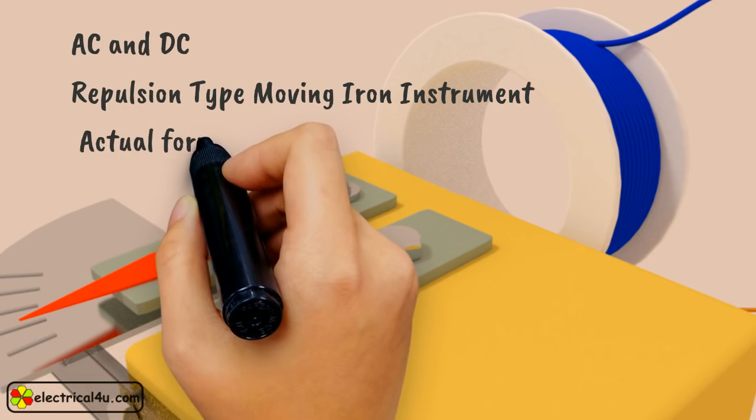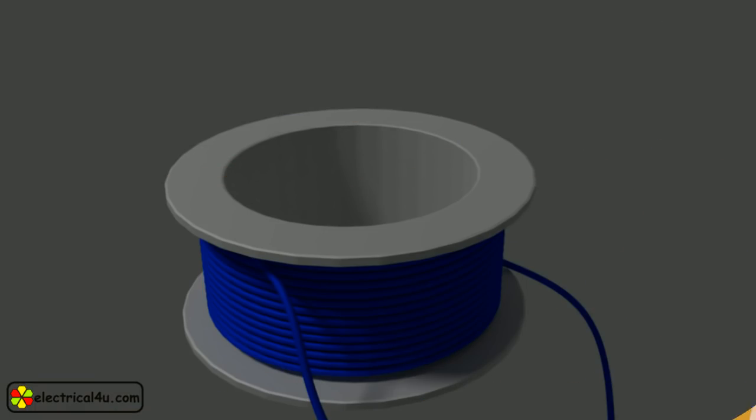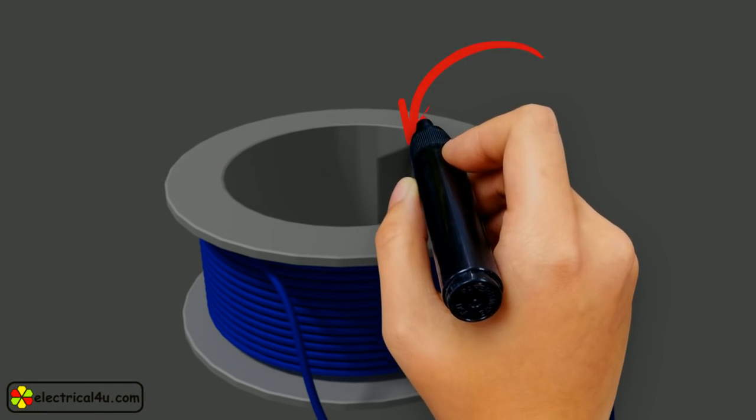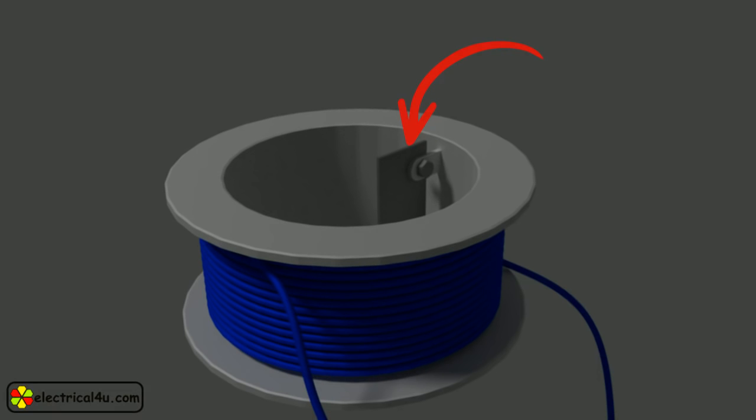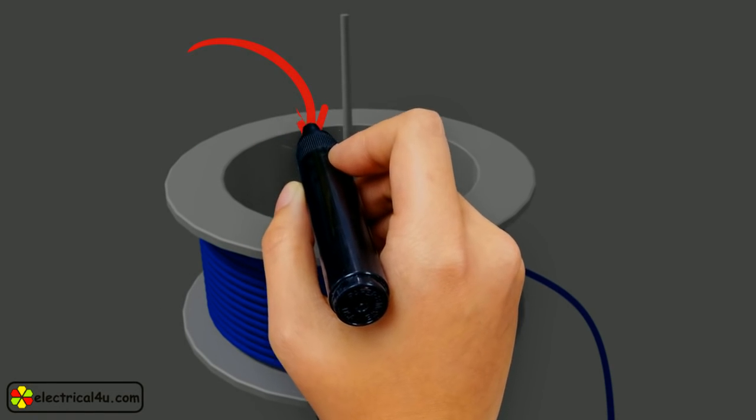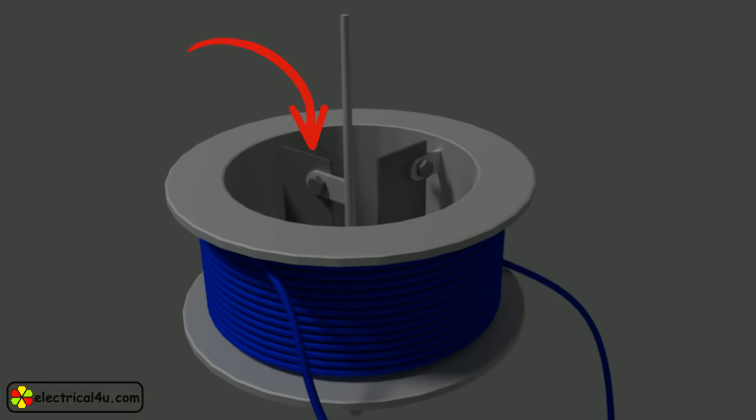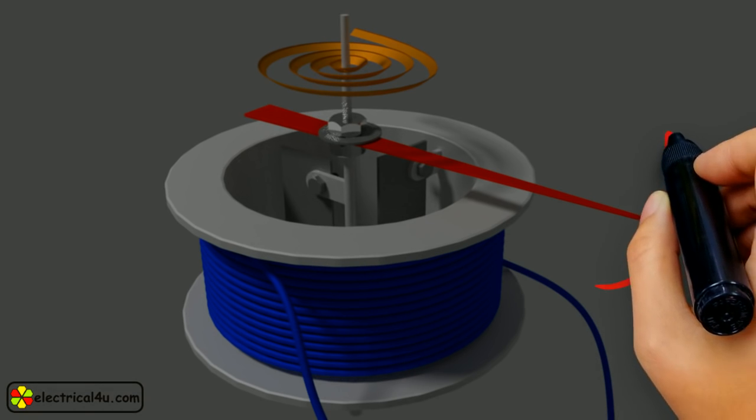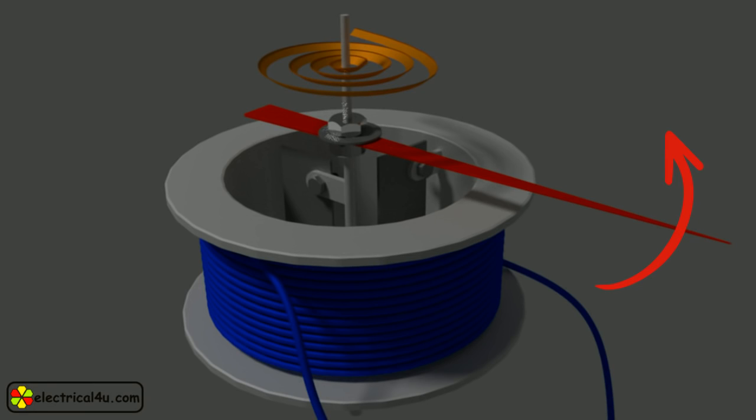Now we will talk about actual forms of repulsion type moving iron instrument. In actual construction, a hollow circular coil is used, and one of the iron pieces is attached inside the hollow coil. The other moving iron piece or moving vane is attached to the shaft. Controlling spring and pointer is also connected with the shaft. As both vanes are placed in the same magnetic field, they are magnetized with the same polarity. Hence the deflecting torque is produced, due to the force of repulsion between two iron pieces or vanes.